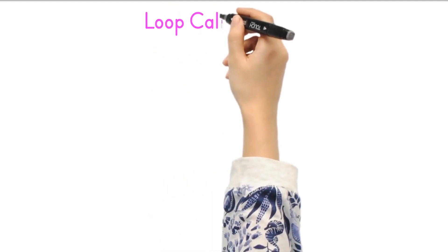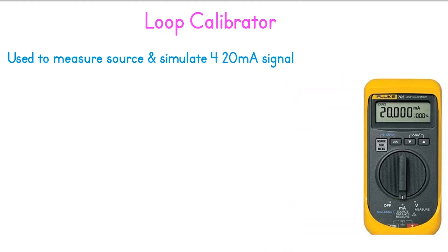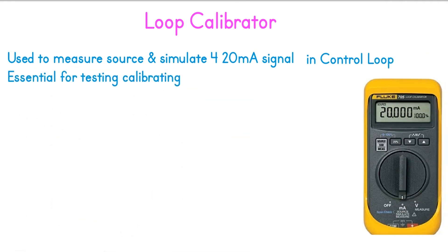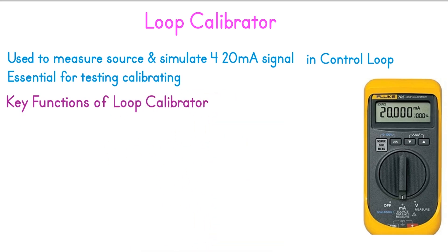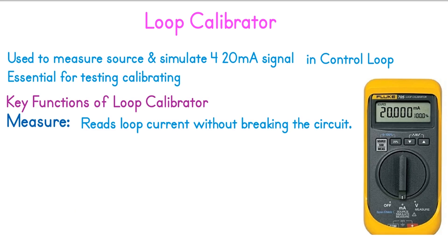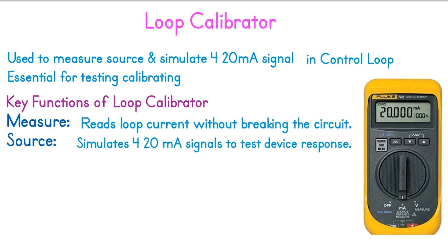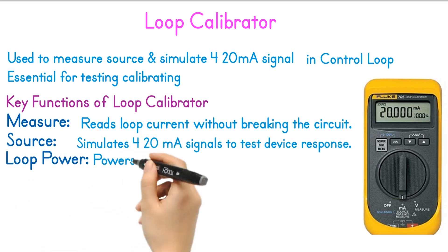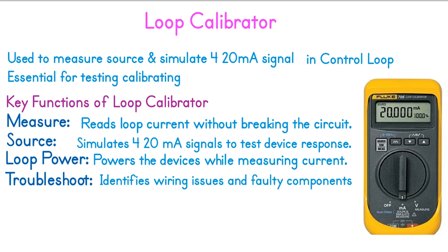Loop Calibrator. A loop calibrator is a portable device used to measure, source, and simulate 4 to 20 mA signals in control loops. It is essential for testing, calibrating, and troubleshooting devices like transmitters, controllers, and actuators. There are four key features of a loop calibrator. First, Measure: reads loop current without breaking the circuit. Second, Source: simulates 4 to 20 mA signals to test device response. Third, Loop Power: powers the devices while measuring current. Fourth, Troubleshoot: identifies wiring issues and faulty components.